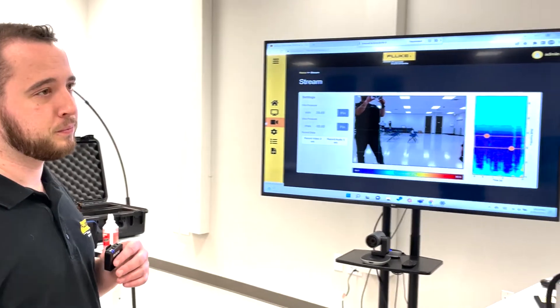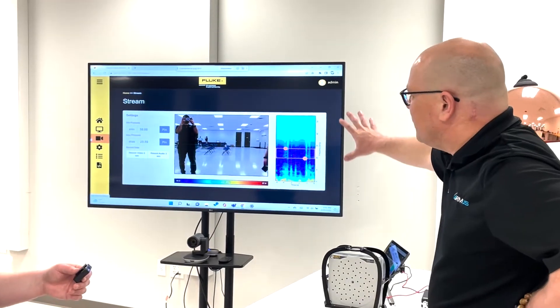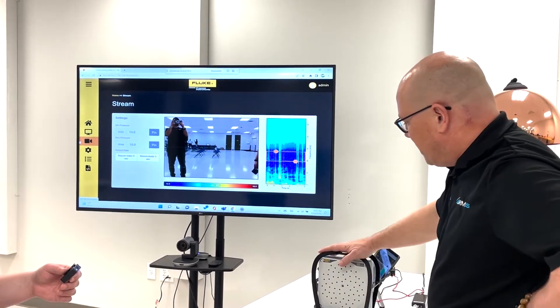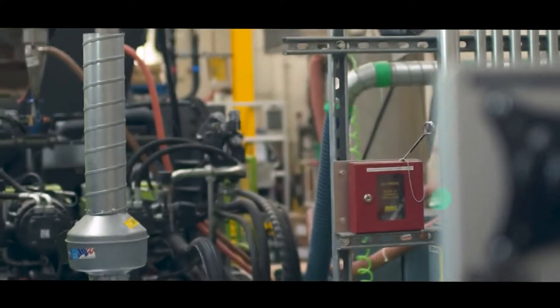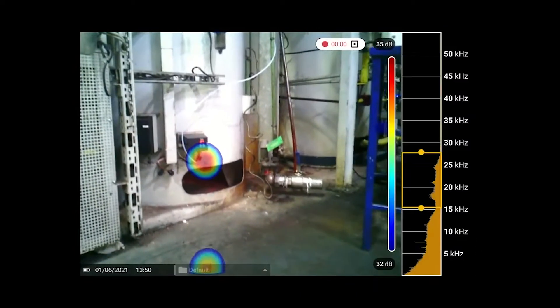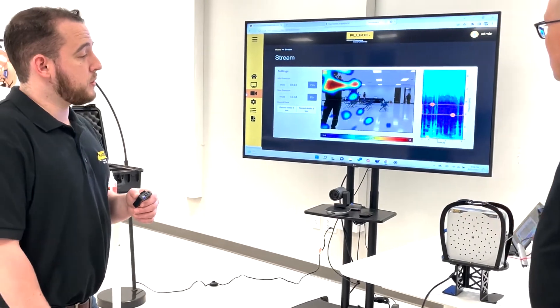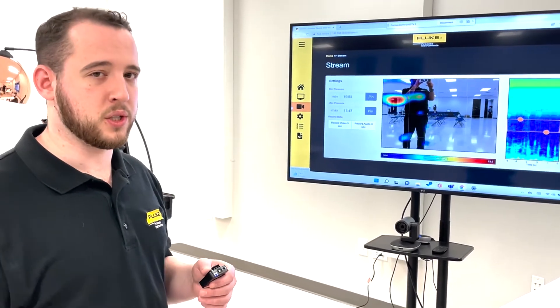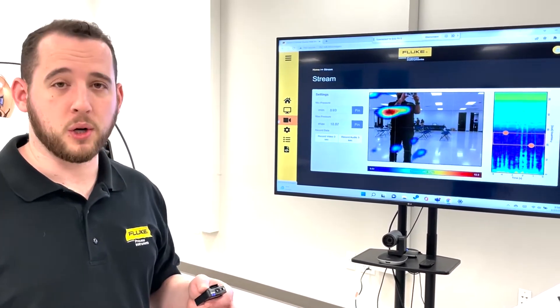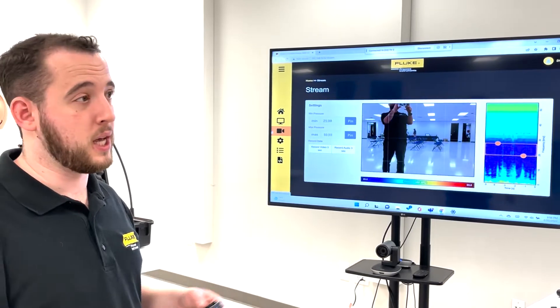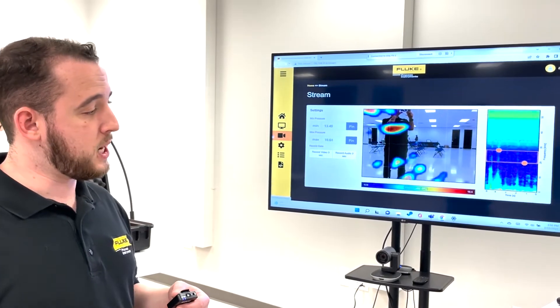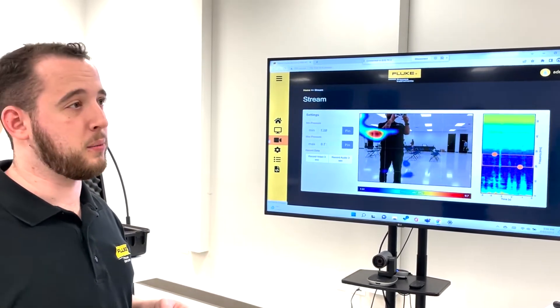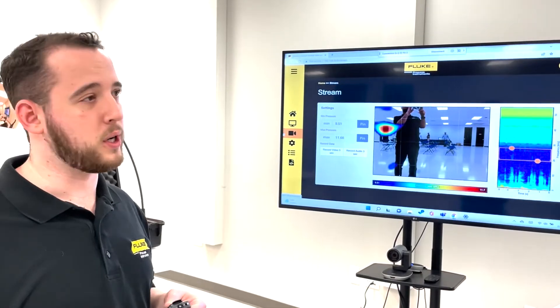So let's say we're in a plant, it's pretty noisy like it is in here right now. Explain how we're going to kind of tune this technology or the software itself. This can be used as a fixed mount and you have some installs already with this. It's also going to be put on Spot with an auto walk feature to walk around the facility or it can be done point to point. So how am I going to tune the software to notice the leaks? Typically what we see in leak detection is that you've got a frequency of around 35 to 40 kilohertz where it puts out a very strong signal. As far as finding those leaks, you would be setting up your auto walk with Spot. You'd have those assets or areas of interest where you anticipate trying to find that leak. Position Spot and the camera in the right direction. You'd be looking along in real time with a device that's connected to the SV600. And from there, the Spot programming takes over. So it'll continue that auto walk, taking a snapshot, an acoustic snapshot at each of those locations.